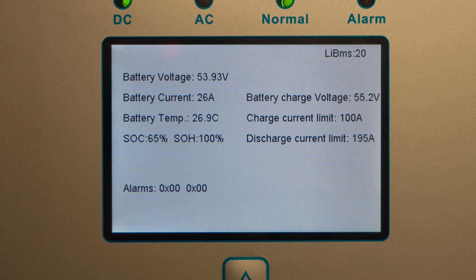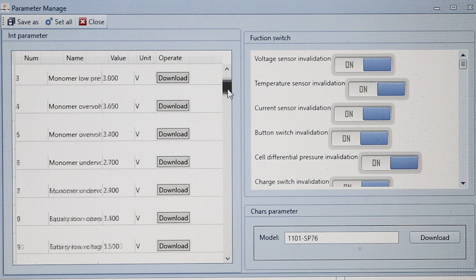First of all, let's have a look at battery charge voltage. So that's the voltage that the inverter is going to charge the batteries at. Well, that's the voltage it's going to send through to the battery. And the question is, where does that come from? If we go over to our BMS program, this is the Seplos BMS program, and this is version 2, BMS that I'm using. I believe the numbers are the same for the version 3, so this should still have relevance. That 55.2 that it's reading comes from item 14. Now I have 55.17 set there, and the SunSync inverter rounds that up to 55.2. You can choose whatever voltage you like for that, and I'll do another video as to why I have that setting as is, but that's interesting to know that that's where that figure comes from.